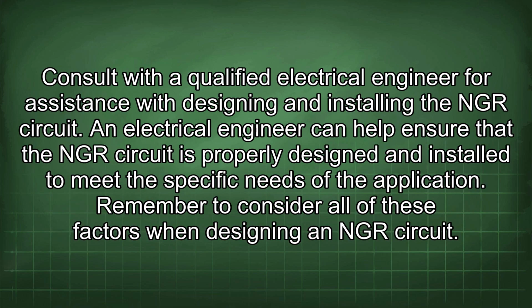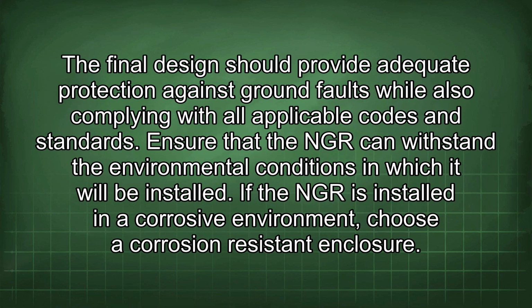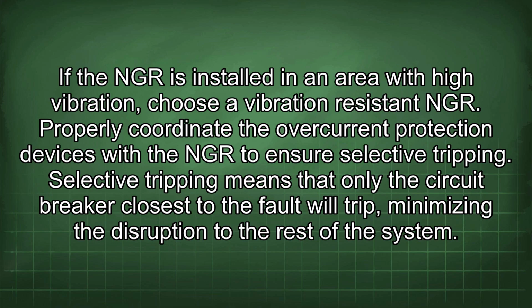Consult with a qualified electrical engineer for assistance with designing and installing the NGR circuit. An electrical engineer can help ensure that the NGR circuit is properly designed and installed to meet the specific needs of the application. Remember to consider all of these factors when designing an NGR circuit. The final design should provide adequate protection against ground faults while also complying with all applicable codes and standards. Ensure that the NGR can withstand the environmental conditions in which it will be installed. If the NGR is installed in a corrosive environment, choose a corrosion-resistant enclosure. If the NGR is installed in an area with high vibration, choose a vibration-resistant NGR.